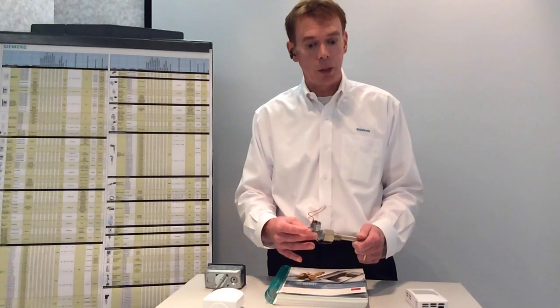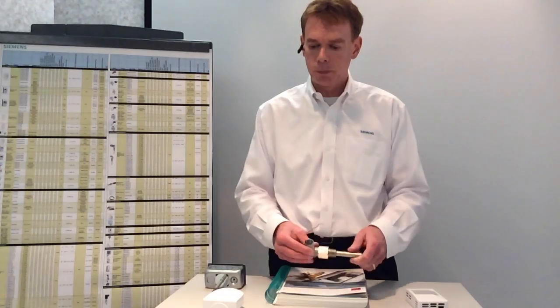The advantage of having the thermal well is if you ever need to replace the temperature sensor, you can remove the sensing element, leave the thermal well in place, and you don't have to drain the system.